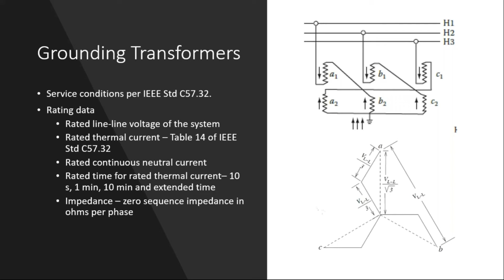And also, the important thing is the zero sequence impedance. So what happens when a current flows in all three phases, which is a zero sequence current, with no phase displacement between them. So this zero sequence impedance has to be specified in ohms per phase, and as per the standard, it's a must. If you specify it in percentage or something else, it can create confusion in the ratings, because the rating for these transformers can create confusion because of the line-to-line voltages. You see, there are two line-to-line voltages which we can see from here, so those confusions can arise for these transformers.